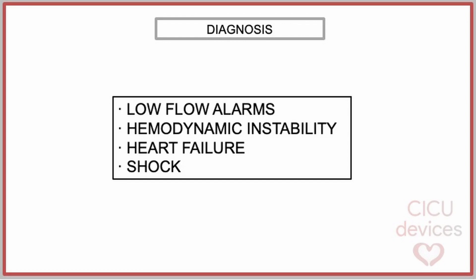Significant clinical manifestations of extrinsic obstruction may include constriction of the outflow graft leading to persistent low-flow alarms or low flow. Persistent low-flow, if not treated, may result in hemodynamic compromise, the need for surgical intervention including possible pump replacement, and risk of death.